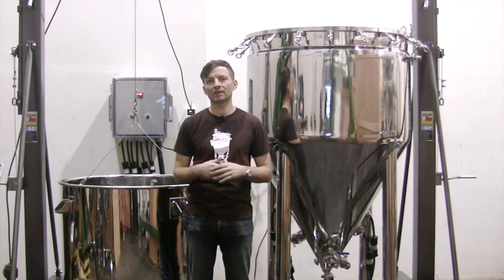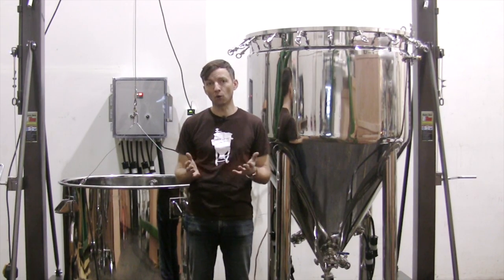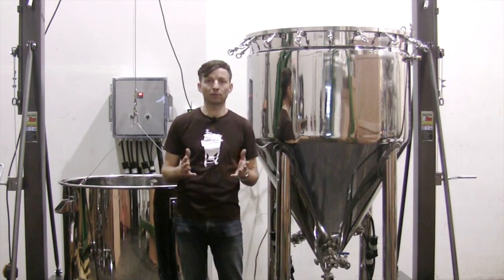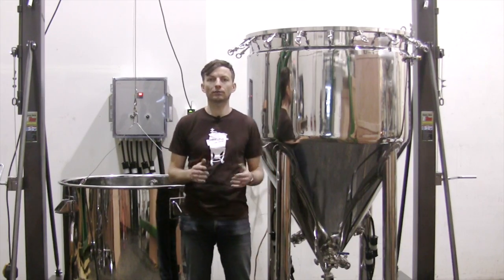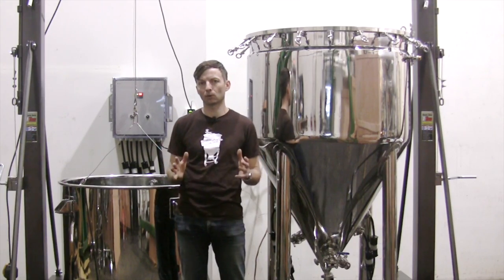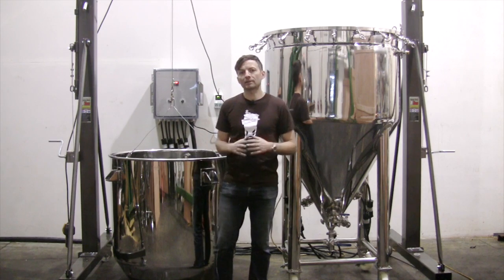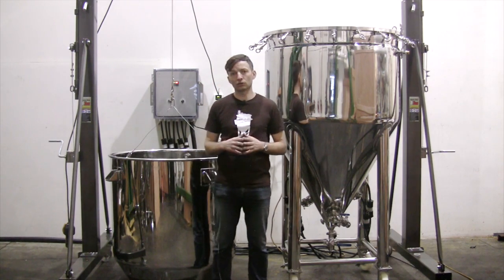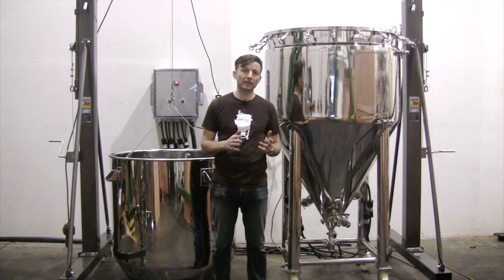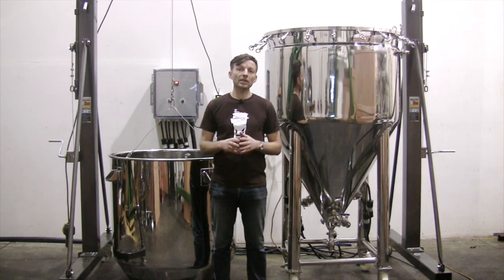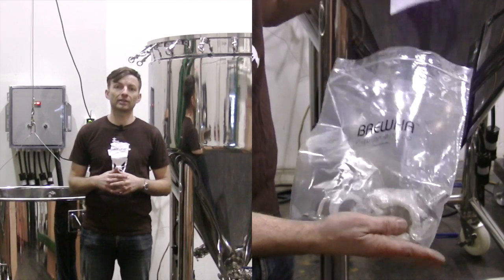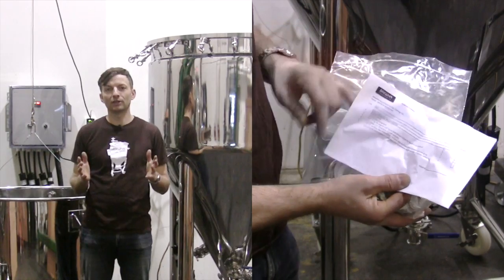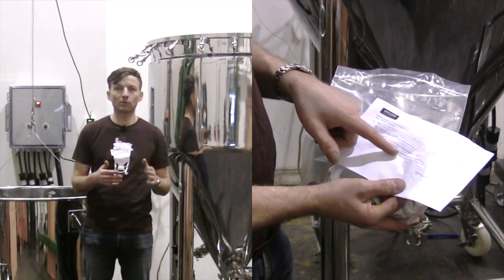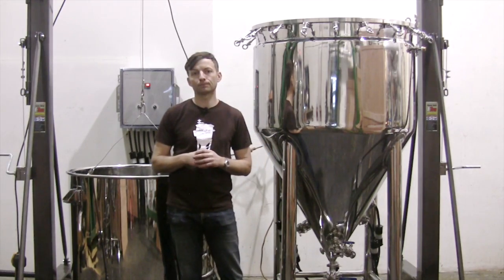If your floor is particularly uneven, you may need to shim the caster plates to level out the fermenter, or if it is impractical to move the fermenter, the casters can be left off and the leg plate secured directly to the floor. With crates unpacked and the fermenter casters installed, we will start by assembling the fittings and valves. Each vessel has a bag with fittings in it for just that vessel, and a packing list inside each bag which describes where the fittings go.